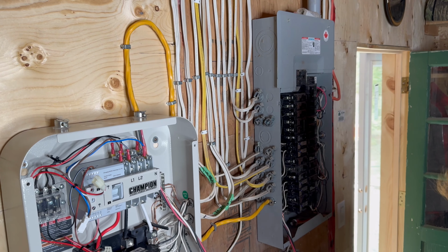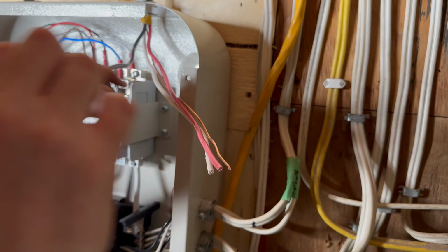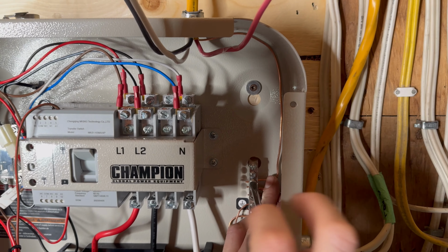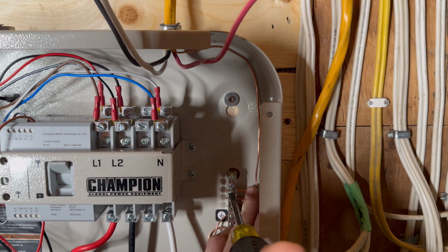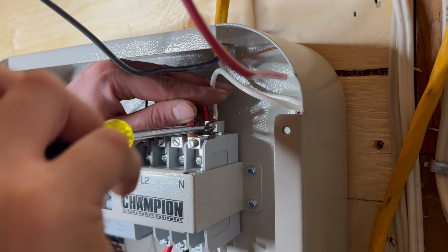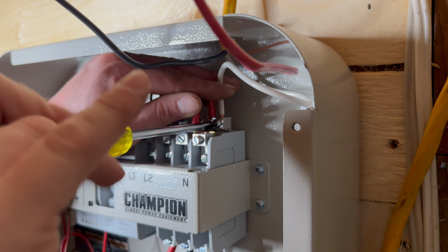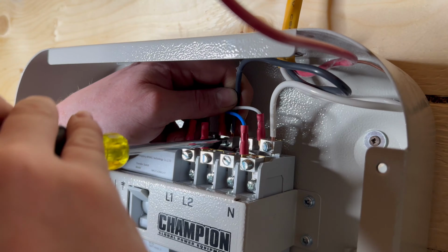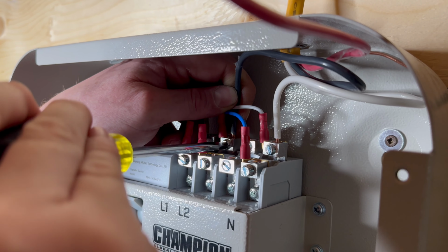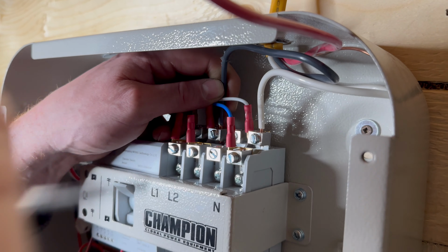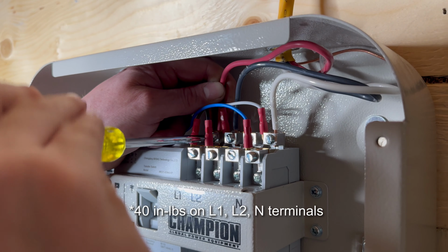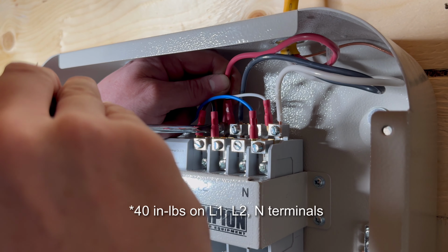After securing the heavy cable with staples, Mark's making the appropriate connections within the transfer switch panel. So that would be the ground wire here. The white neutral is going to go to the N lug, and the 2 hot wires, in this case the black and red, will go to the L2 and L1 lugs. Be sure to tighten these to the appropriate torque.